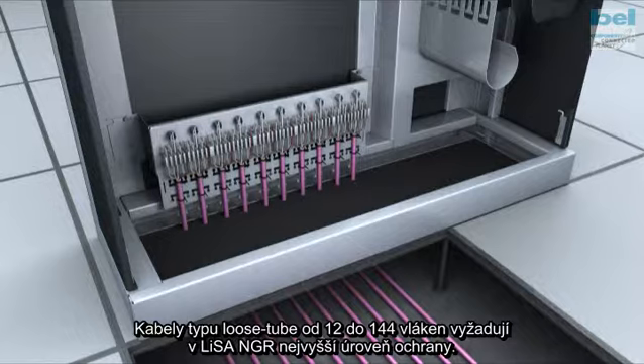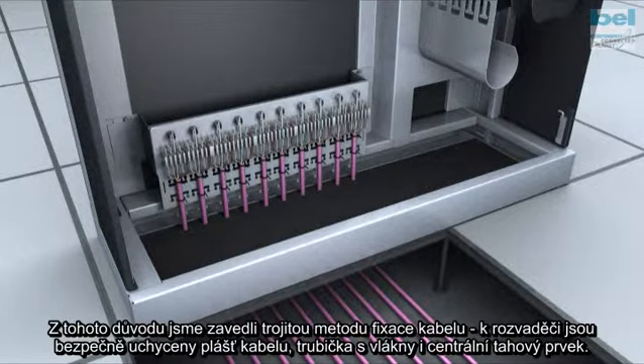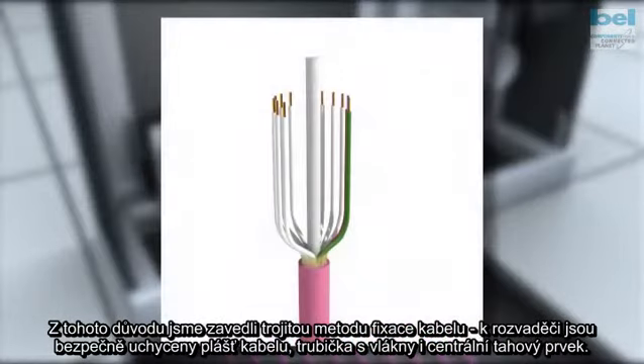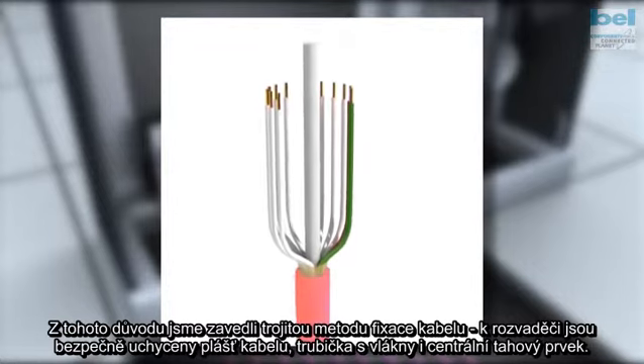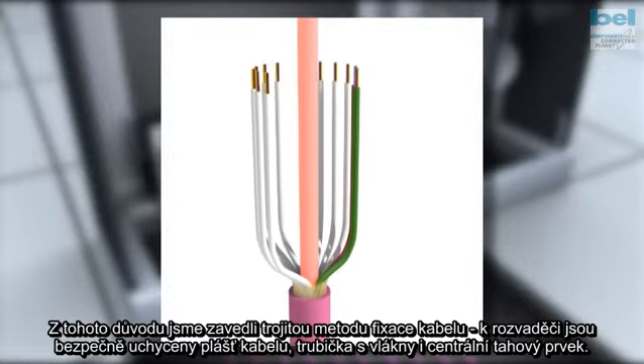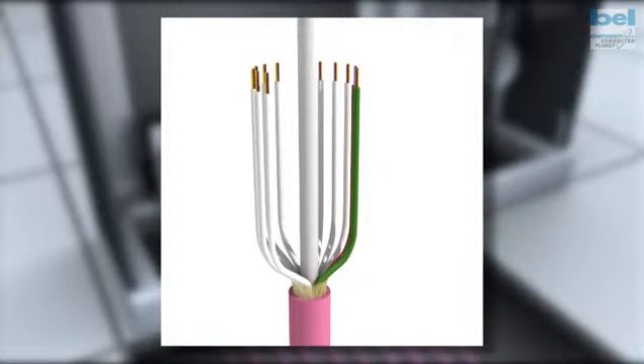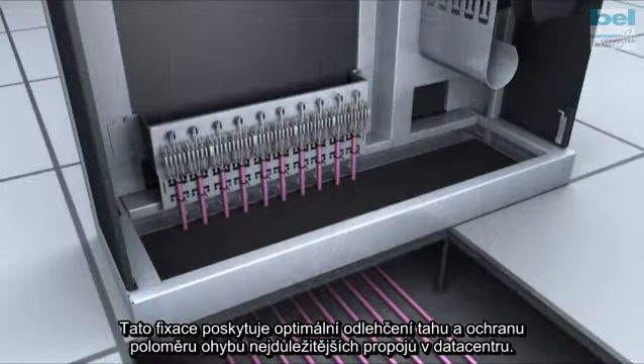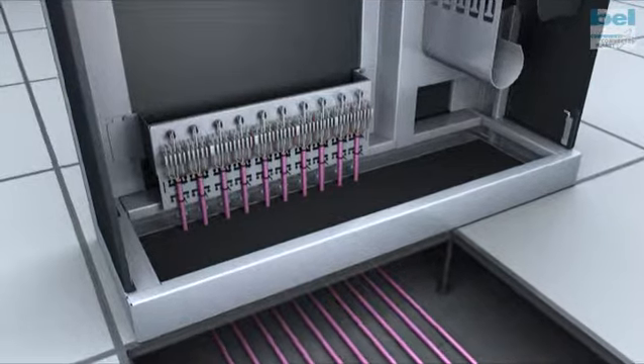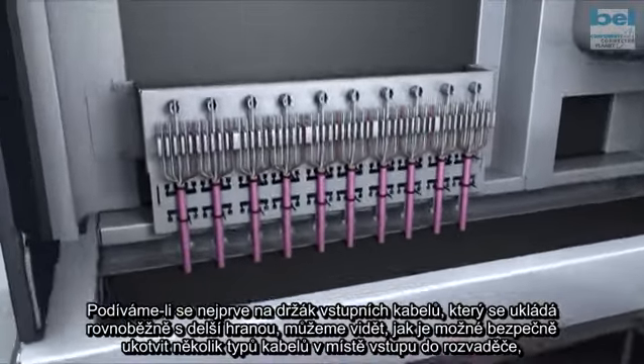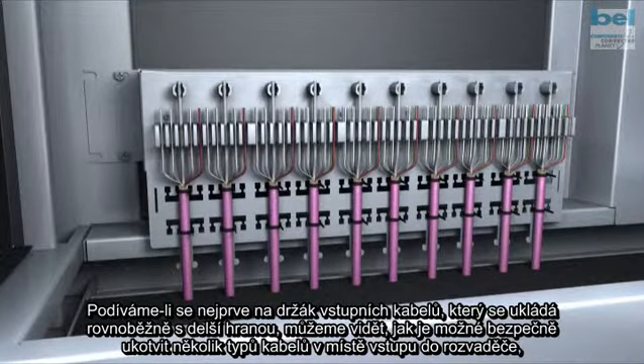Loose tube cables from 12 up to 144 fibers require the highest level of protection within the LiSA NGR. For this reason, we deploy a 3-tier fixing method whereby the cable jacket, loose tube and central strength member are securely fixed to the rack. This provides optimum strain relief and bend radius protection for the most important links in the data center. If we look first at the full width breakout plate, we can see how multiple cable types and fiber counts can be securely anchored to the entry point of the rack.